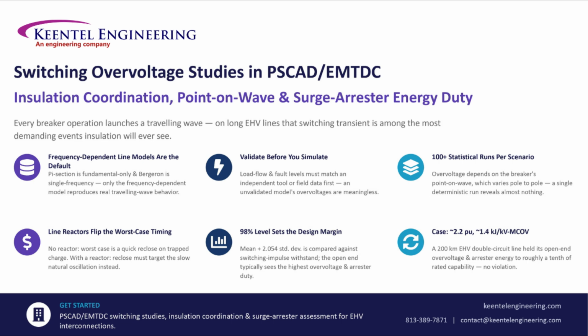Before any of those results mean anything, though, the model has to be validated. Load flow and fault levels checked against an independent tool or real field data. An unvalidated model's overvoltage numbers are essentially meaningless. And because overvoltage depends heavily on exactly where in the voltage cycle each breaker pole closes, a single run tells you almost nothing. These studies run statistical sweeps, often more than 100 per scenario, to find the real worst case.